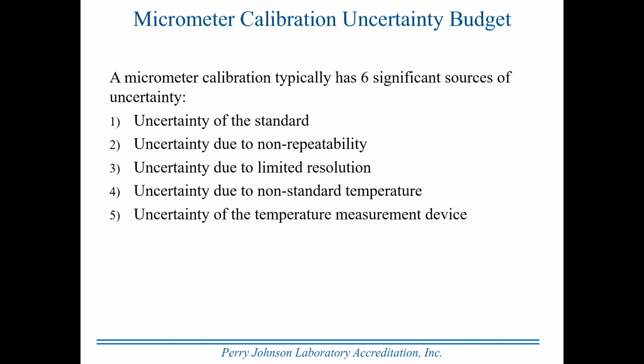Uncertainty of the temperature measurement device. Here's another temperature sensitive contributor. The temperature of calibration is being measured with a temperature device, which itself has to be calibrated, and as a result, it has its own uncertainty associated with its calibration. So just like the standard that we use has calibration uncertainty, the temperature measurement device does as well. And then the last one is uncertainty due to differential temperature.